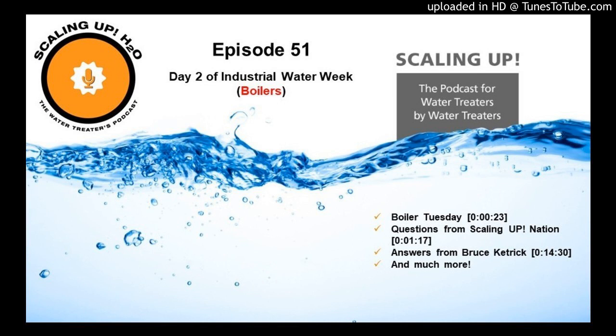Now, depending on how long that boiler is being set up, we need to test that on a regular basis, because it's all that product that we have in there, it's going to get used up, and we have to replenish that. And I've seen a lot of people that will wet store a boiler and leave it there for years. Folks, it doesn't work that way. The reason we all have a job is because those products get used up, and we're the professionals that need to know how much product to put back in there.